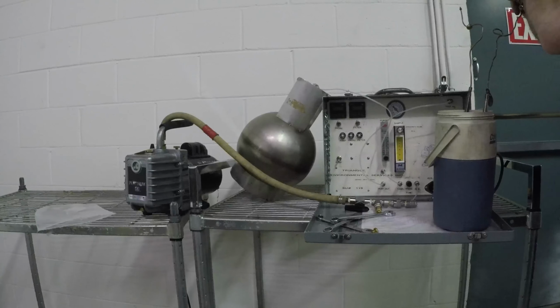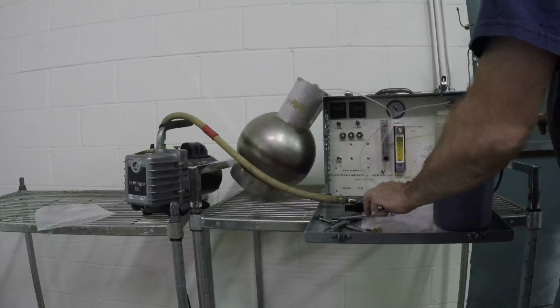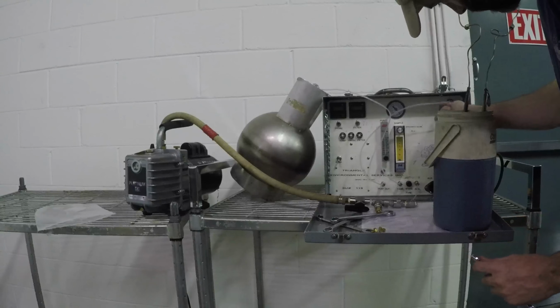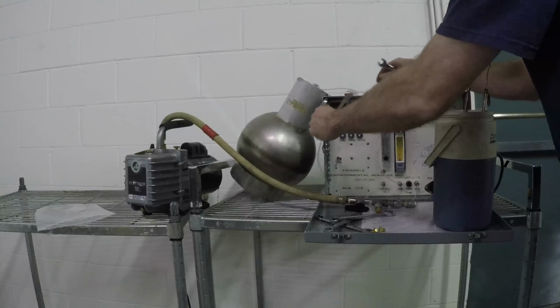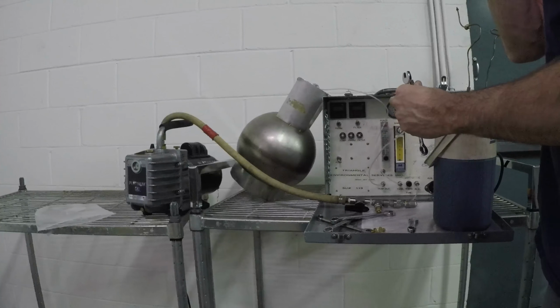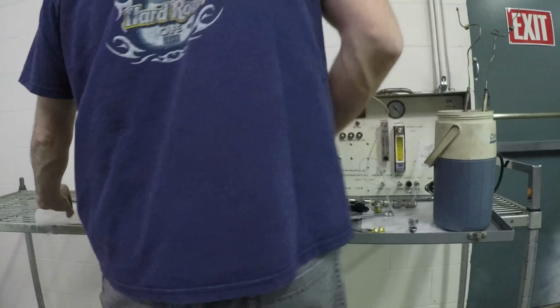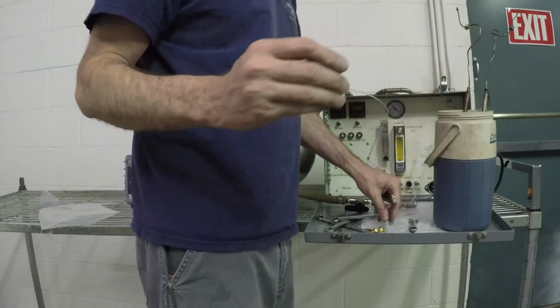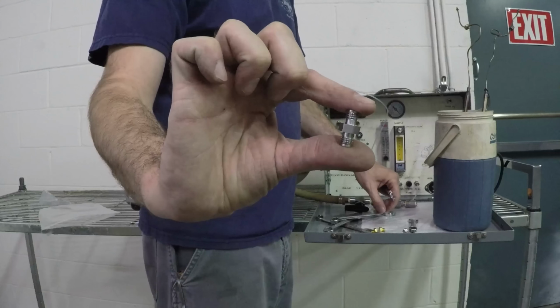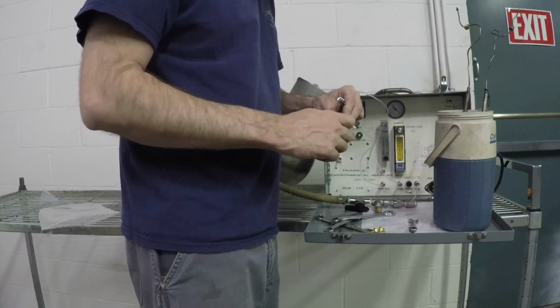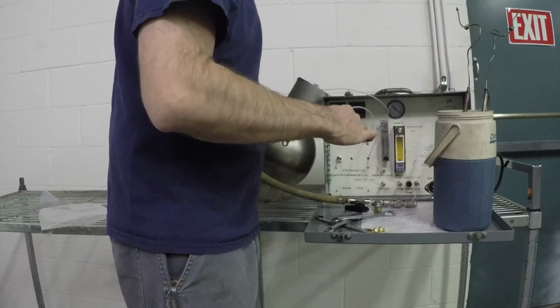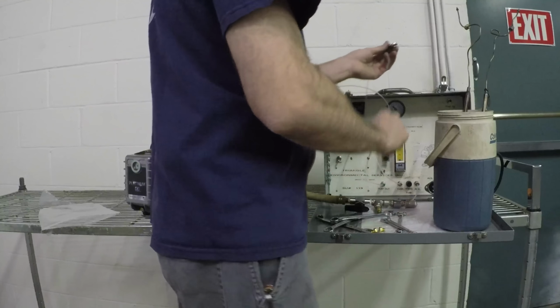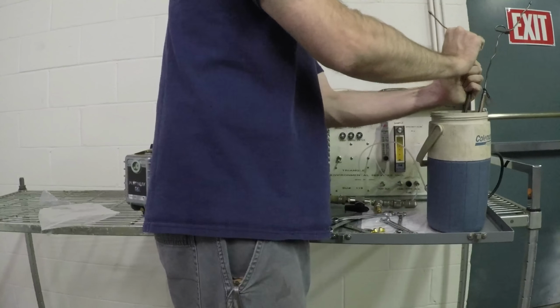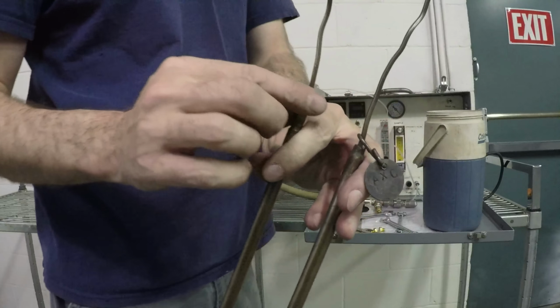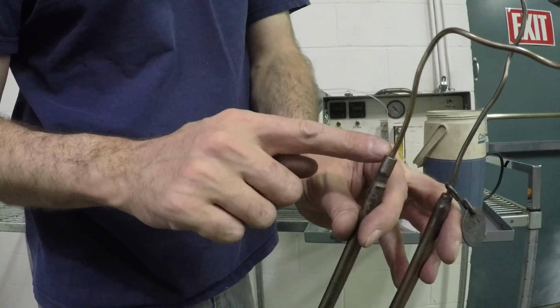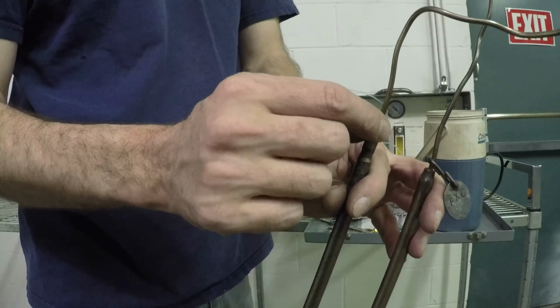Plugs. Disconnect the trap in line here at the bulkhead. Reach into your spare parts kit, where you will pull out an 1/8 inch union, attach it to this line, and it attaches to the short end of the trap. When you bend your trap, never bend right here at the weld. It is the weakest point on the trap, and it is where they fail the most often.